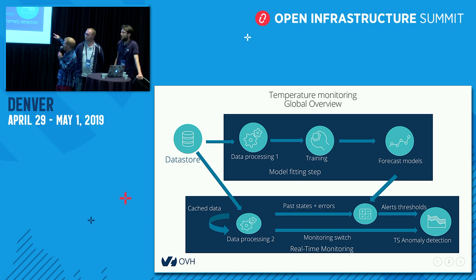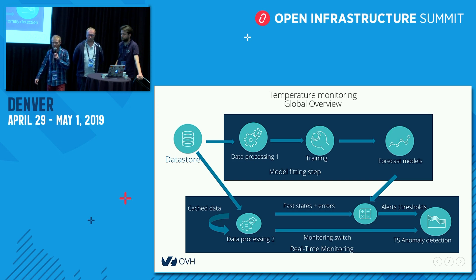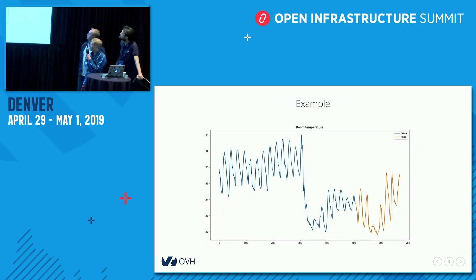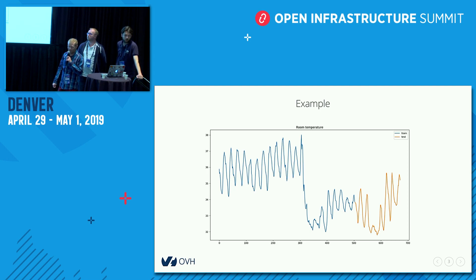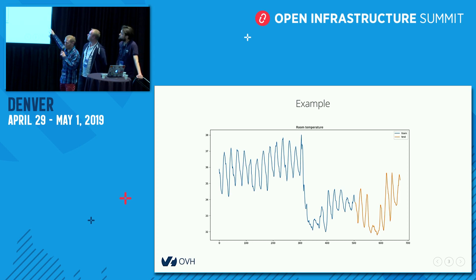We generate dynamic forecasts and then compare the forecast temperature to the real one observed. If the real one goes too far away from the forecast, we raise some alerts. Let's illustrate with a real example. This is the temperature curve of one of our rooms in one of our data centers. We train the model on the blue curve — the temperature history — and evaluate it on the more recent history, the yellow part, to determine what the thresholds should be. Then we use the trained model to generate out-of-sample forecasts, the points in the future on the right of the plot.